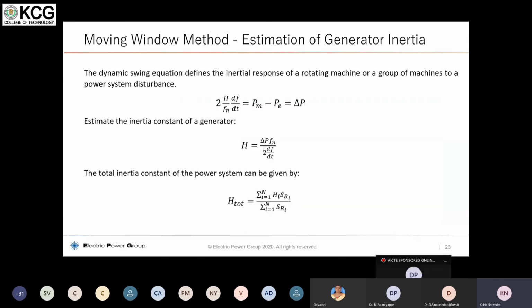Now in the first method, as I said, for the dynamics of the system equation, of course, we have made some assumptions here. The damping and other things are neglected, which is a fair assumption to get more conservative results. But it's an absolutely viable assumption. If you take that and look at the way you evaluate H, the inertia constant, and the total inertia constant, you can evaluate it whenever a disturbance happens in a system, identifying the disturbance starting point. As I said, the only support available to the system during that time is inertial support. Therefore, the evaluation of H will be pretty good in that region of below 10 seconds. Okay, so this is the method we have followed.